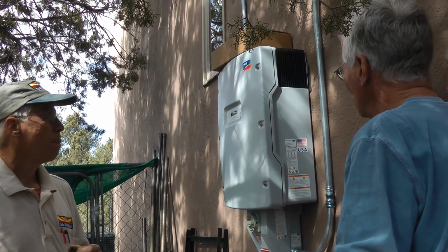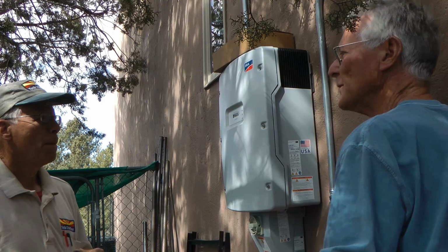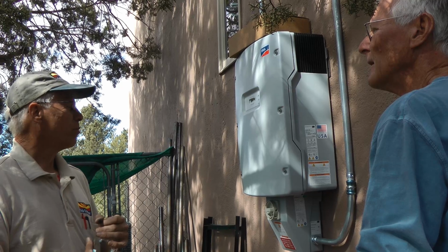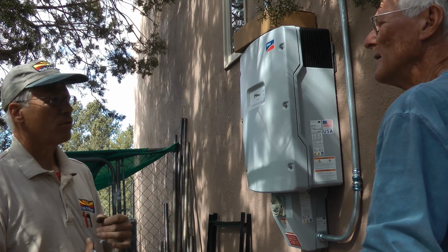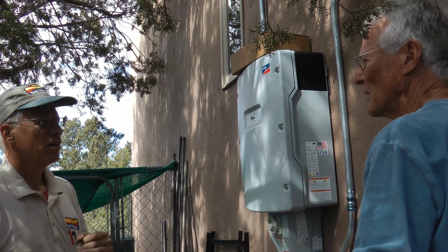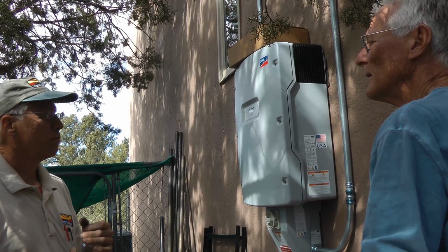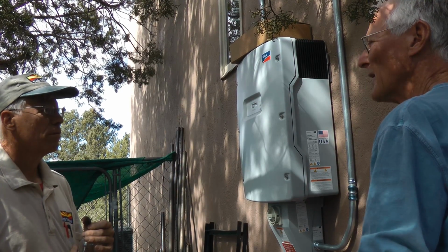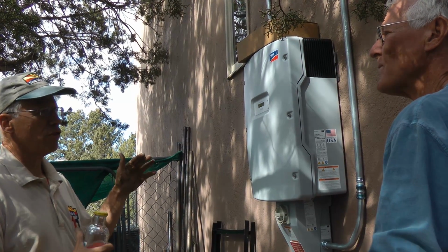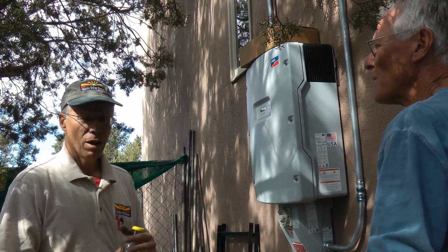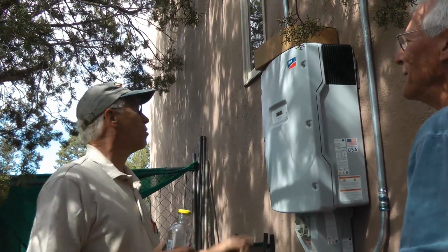And will it read out in watts or kilowatts? Initially it'll start out in watts, but it'll get up into kilowatts. It'll say kW. So it'd be like 5.1, or 5100? Yeah, it'll give you 4 digits. Okay, so it's accurate. Yeah, and then eventually it'll get up into a megawatt of cumulative energy. Oh, cumulative, right. I had one guy call me up saying there's something wrong with the inverter, it's only done 1 kilowatt. I get out there, and no, that's 1 megawatt. It's flipped over after about a year or something.